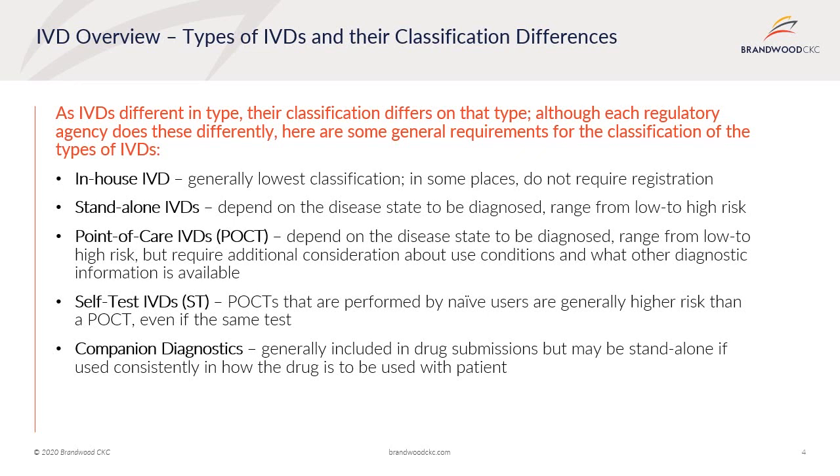Now, what I will say is that overall classification of IVDs, no matter what the geography, are based on 2 assessments. One is their public risk, so whether the disease that's being diagnosed is of a public risk. So if we talk about something like Ebola, HIV, or something that's done for blood screening, it's a higher public risk. So those are higher classifications for those devices.